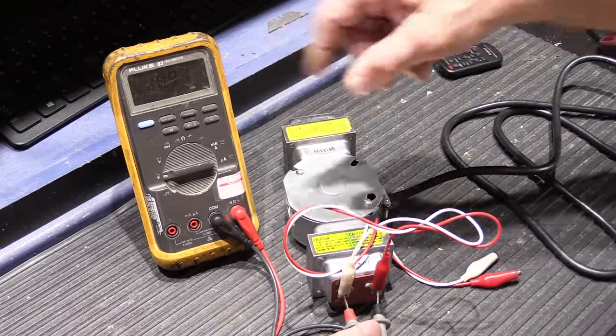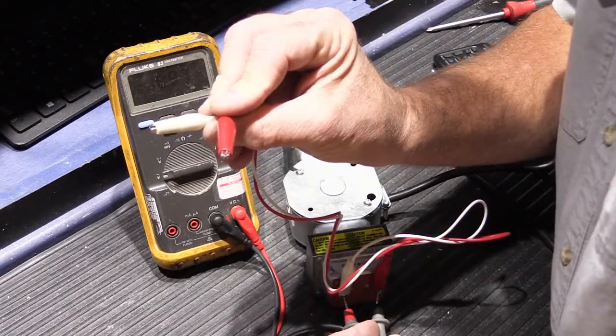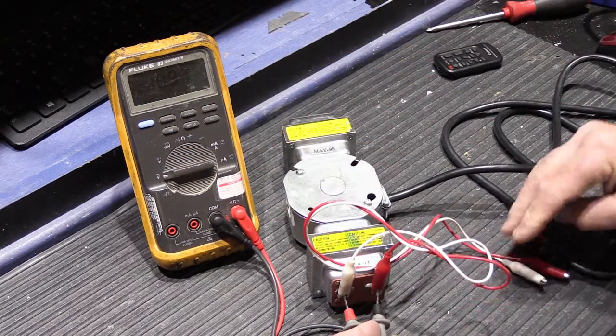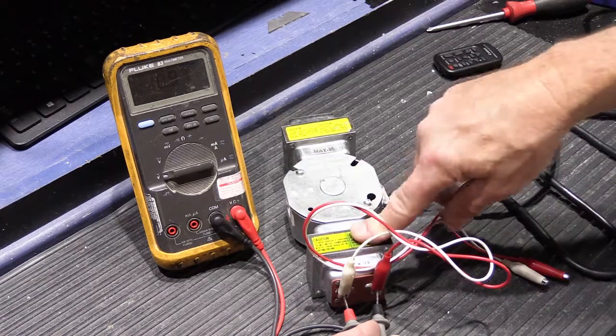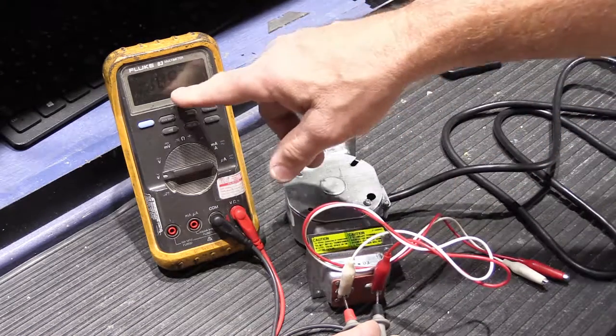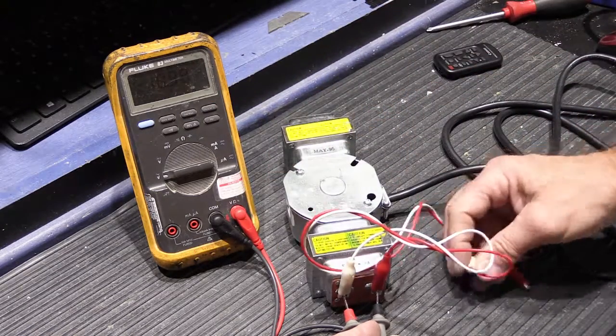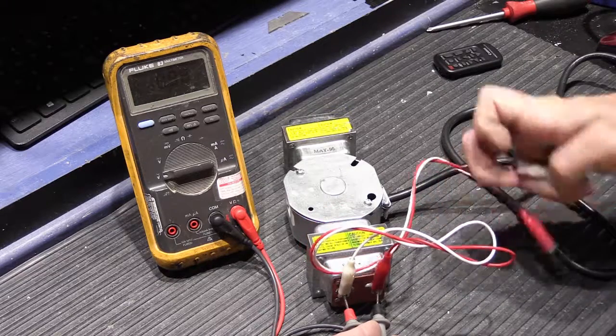What I'm going to do is touch the other ends of the test leads together, creating a dead short, which will overload the transformer, and we're going to watch what happens to the voltage. So here we go.